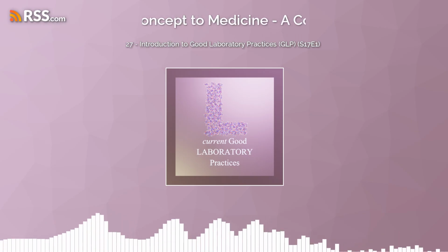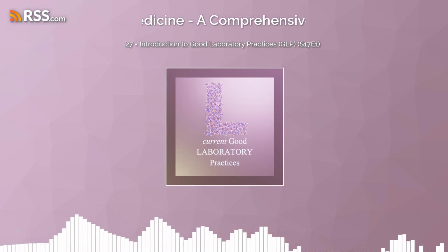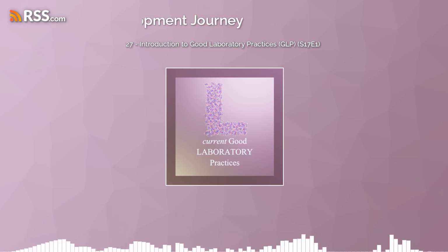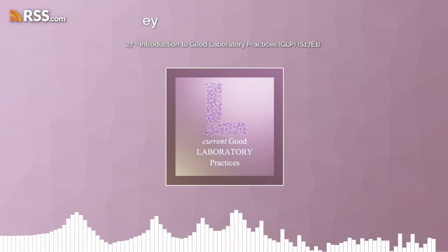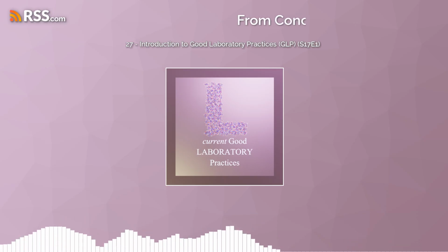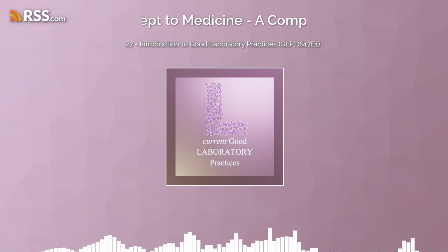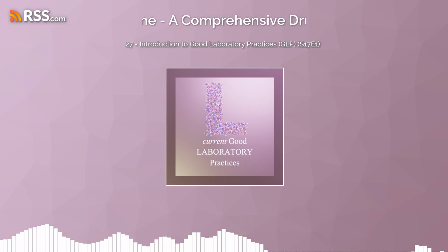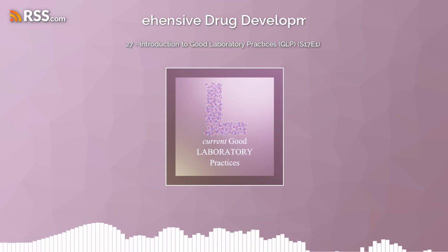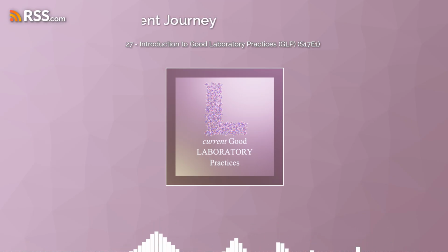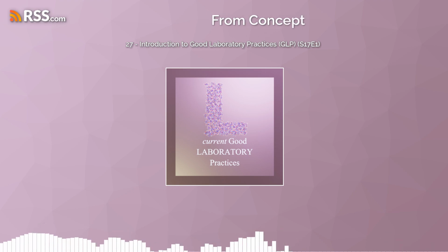Right. And then there are all the other controls we need to think about. Ventilation, air filtration, controlling air pressure, monitoring microorganisms, dust, humidity, temperature. So many things to keep track of. It's a lot. And of course, we have to handle lab waste properly, treat it, and dispose of it safely to prevent contamination. It sounds like a huge job just to maintain the right environment. It definitely is. And don't forget about equipment qualification. We need to make sure that all our instruments are not just working, but working correctly in that controlled environment. Because a malfunctioning instrument could give us bad data, even if the environment is perfect. Exactly. So it's all connected.